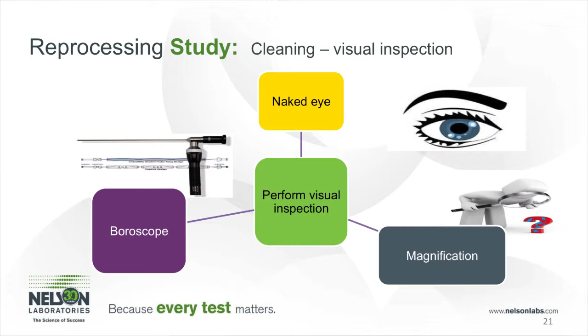After the cleaning procedure is performed, next is the visual inspection. Until just a few years ago, visual inspection with the naked eye under normal lighting conditions was the normal visual inspection performed on medical devices. As of the arthroscopic shaver issue in 2009, it has become more evident that we need to make sure that we're testing the inside of devices to ensure that the inside of devices are also clean, because those obviously cannot be seen by the naked eye.